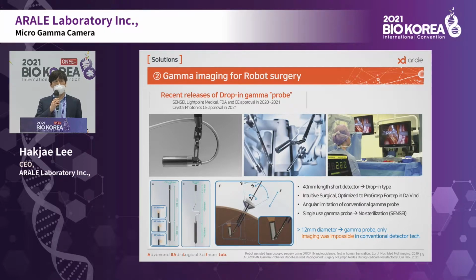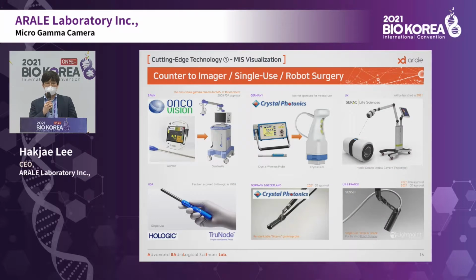Another device is the probe. When it is used in the robot or in operation, the angle was difficult. So in order to solve this problem, the gamma probe was attached to the robot and recently received approval from the FDA. And now it is commercialized recently. So this has the gamma probe type. The dose rate or the signal can be shown in number or sound. However, it doesn't provide any imaging yet.